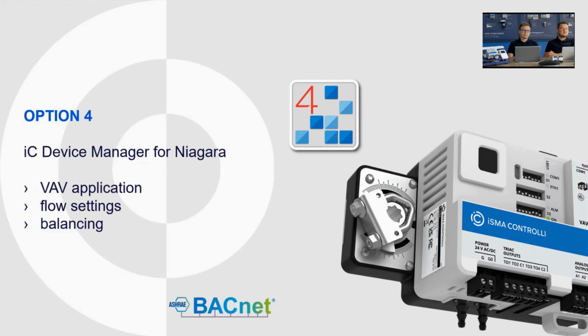All right, great. So the other option we have for the Niagara users, coming with our latest IC Niagara 4.15.1, is that the IC Device Manager will become available to you integrated into our Workbench, but we will always release it also as a free of charge service for users that use any Niagara Workbench. So this is an extension for your Niagara Workbench of choice that gives you the capability, while seeing all the devices on the BACnet network, to also easily access the application configuration.